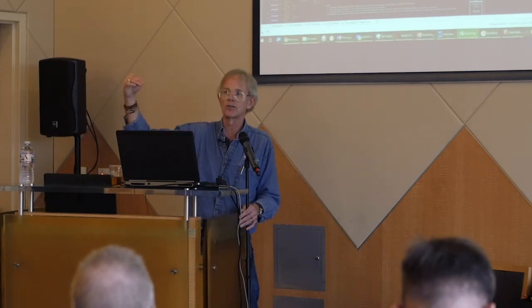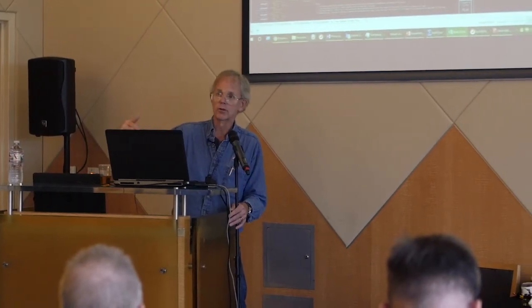So this is basically a control logic for a modulating bypass valve and a 2-speed tower fan, which is essentially what you're talking about, right? You modulate the valve and then you have to step the fan on and step it off. And so the way this logic works is the output of the loop modulates the valve, and then the output of the loop goes to what amounts to electronic relays, and you can control the set point of the relays to control when the fan stage is on and when the fan stage is off. So not only could you play with the tuning of this loop, you could play with those set points and the spread between the set points to manage how quickly or not things happen. Loop still has to be stable, but you can control how much drift you're going to get between stages and stuff that way. I don't know, does that help?